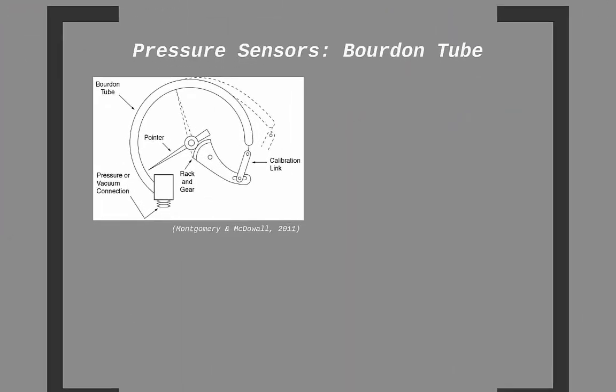Speaking of pressure sensors, let's look at a few different styles. The Bourdon tube is quite common. It is used to measure gauge pressure, which is the difference between the fluid's total pressure and that of the local atmospheric pressure. Such a device works by filling the inside of the Bourdon tube with the fluid whose pressure is being measured. The higher pressure inside the tube will cause it to extend, similar to those blow dragons you see at kids' birthday parties.